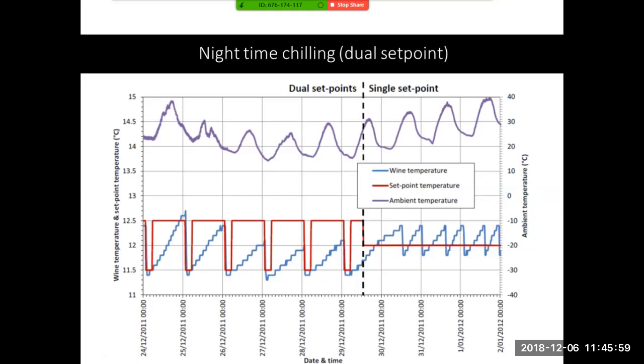This technique was really effective at shifting refrigeration into off-peak periods, and the wine still only fluctuates within a 1 degree temperature band, so you don't really have to worry about wine quality. The set point temperature is still set, so if it rises too far above it, the refrigeration system kicks back in anyway. It's really effective, and quality isn't a concern because it's managed automatically by the system.